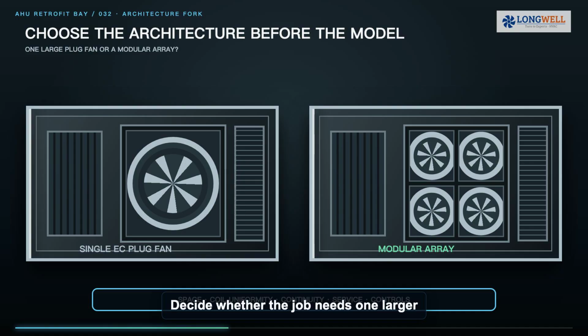Decide whether the job needs one larger EC plug fan or a modular array. An array can help when the cabinet is shallow, airflow distribution across the coil matters, or service continuity is required. But it also adds wiring, protection, controls, and interaction between fans. Choose the architecture from the AHU constraints, not from a fashionable layout.